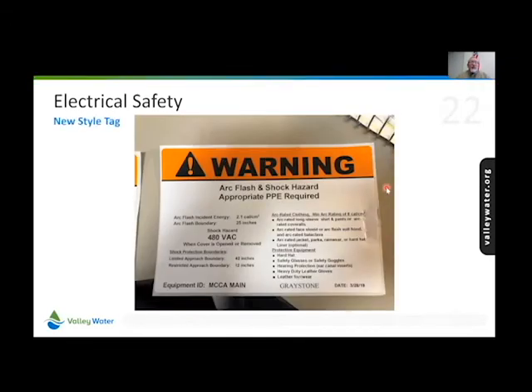Next slide, you can see now we're dealing with an incident energy that's above 1.2. This was 2.1. So it lists all the types of clothing you need to be wearing for arc rating: an arc rated long sleeve shirt and pants or coveralls, an arc rated face shield, a balaclava, which is actually like a sock you use out in the snow that covers your head completely, and an arc rated jacket or parka, or they even make arc rated rain gear now. On top of that, again, the hard hat, safety glasses, hearing protection, leather safety gloves, and they want to make sure you're also wearing leather footwear.